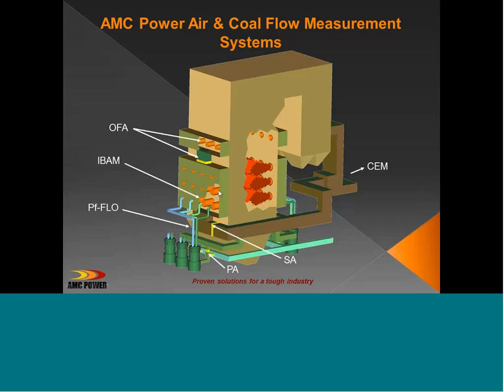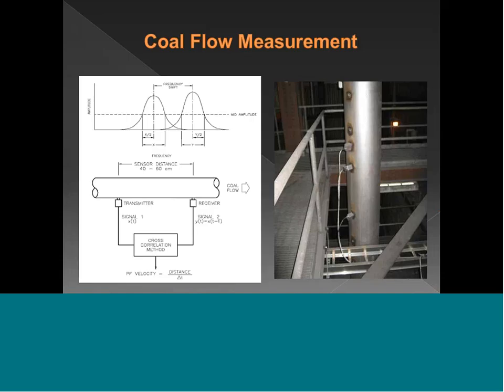With all the extra air years ago down here, if we had a burner running substoichiometrically, extra air could be delivered to it. Now if it's substoichiometric, you're going to be making CO, you're going to be making unburned carbon, and you're going to be trashing your water walls. So individual burner air and fuel flow measurement has become much bigger since the advent of overfire airflow systems.